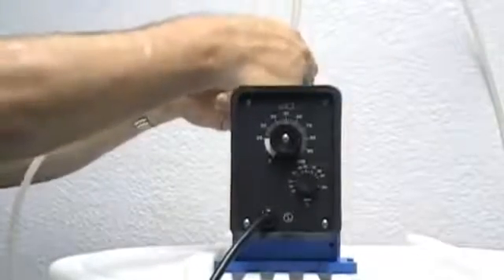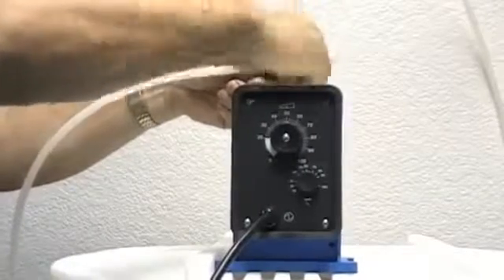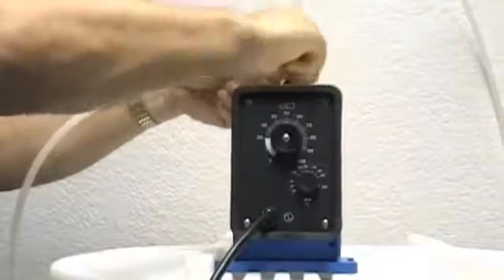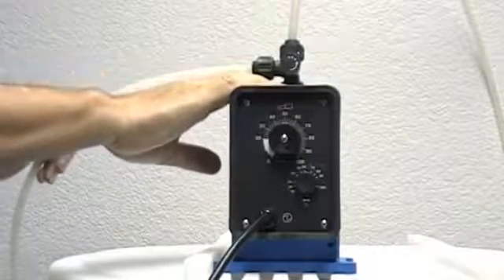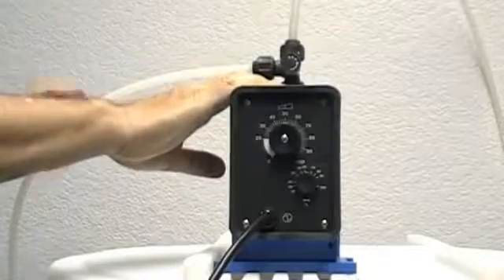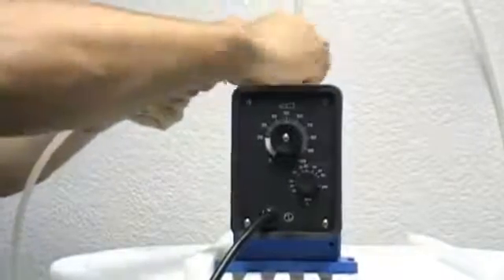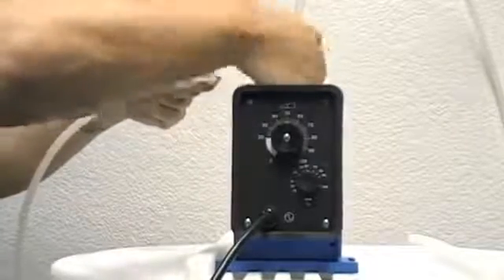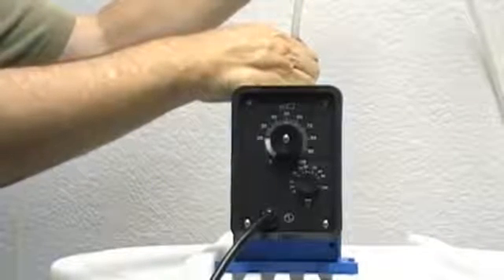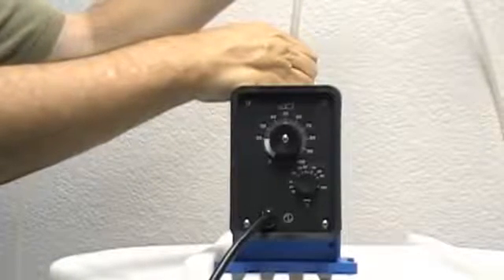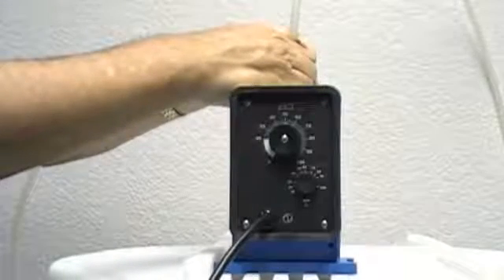At this point you're ready to use the bleed valve. Open the bleed valve by turning counter-clockwise. This will allow your liquid to flow out the return line and into your tank. Once you have a steady stream of pulsating liquid, close the bleed valve. This causes the liquid to flow out the discharge side of the bleed valve and into your injector. It may take one or two minutes for the liquid to fill this line.